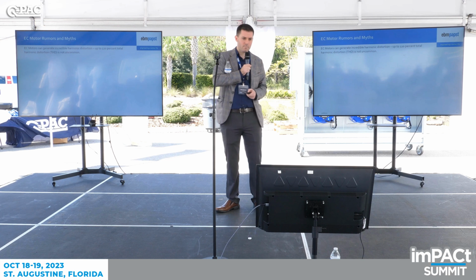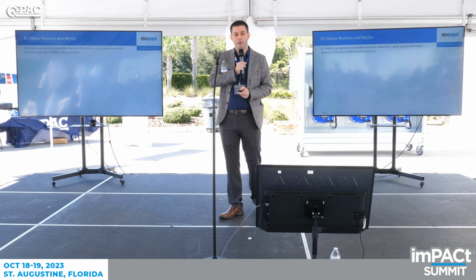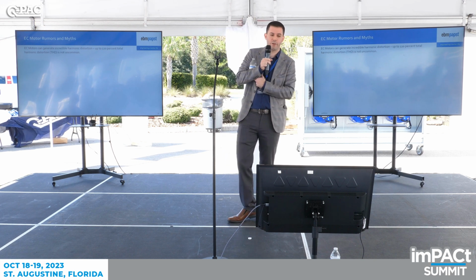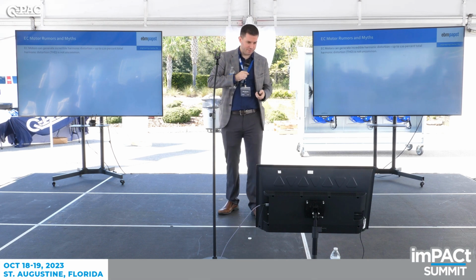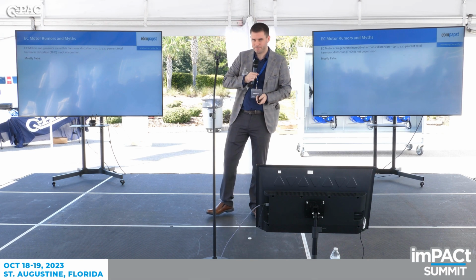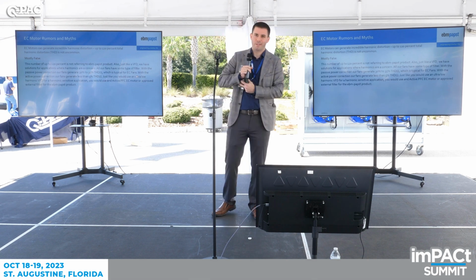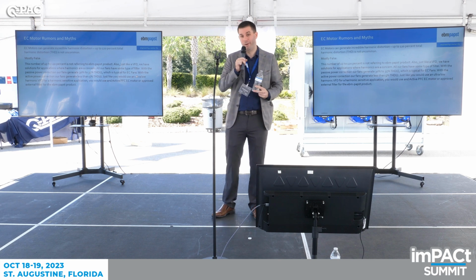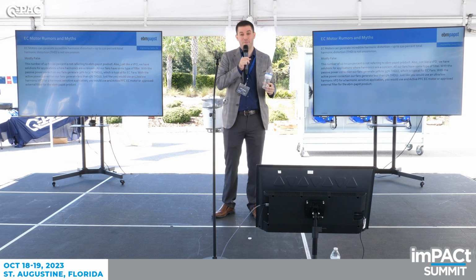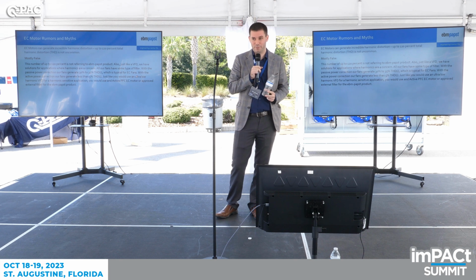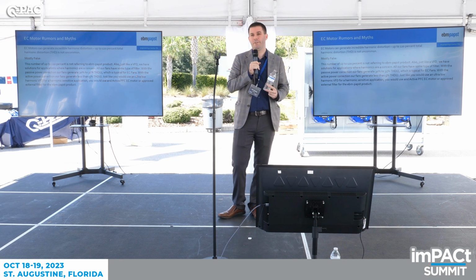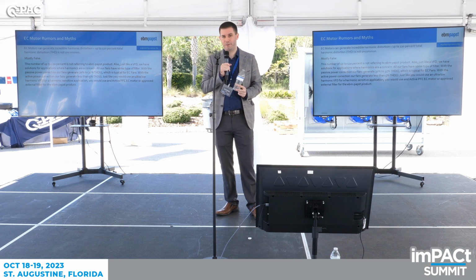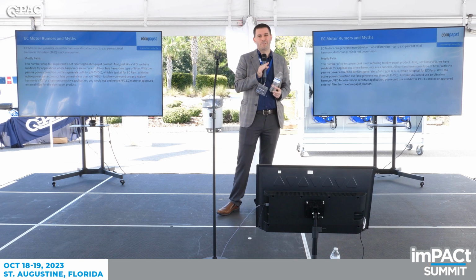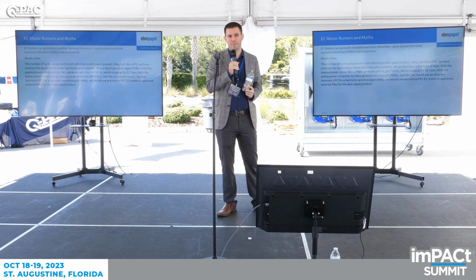EC motors can generate incredible harmonic distortion, up to 120%. Okay, so this one I say mostly false. The reason I say it, I work for EBM Pabst. I don't know every EC motor that's in the market. Maybe some of them do generate 120% harmonic distortion. Maybe some of the ones from Asia, I don't know. But I could tell you, ours isn't going to be generating 120%. Full load, ours is normally around 30 to 35%.